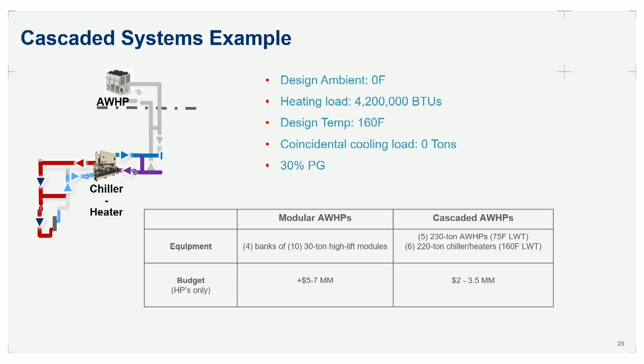Now, if you take that same condition, those same exact loads, and split it up using the system diagram shown here, a standard air-to-water heat pump as the first stage and a standard chiller heater on the inside, we can reduce that cost by about half. Because now each piece of equipment operates in the highly optimized operating map it was designed for, instead of selecting equipment at the limits of its capabilities and forcing it to hit the temperatures we need.